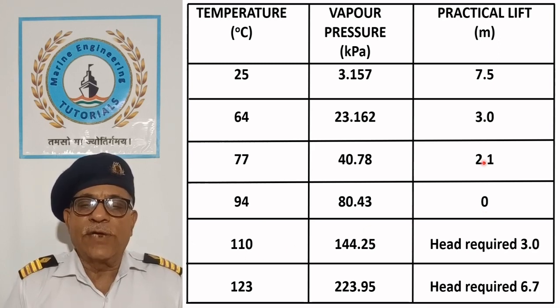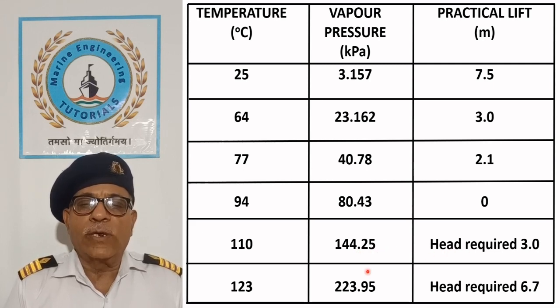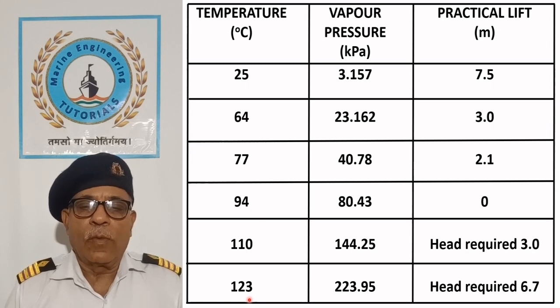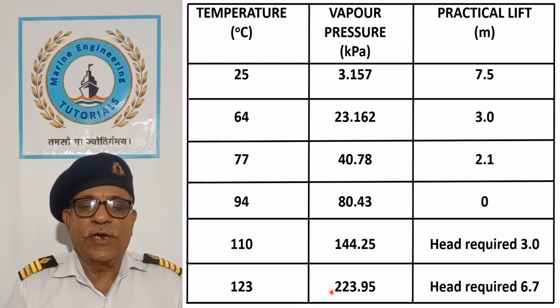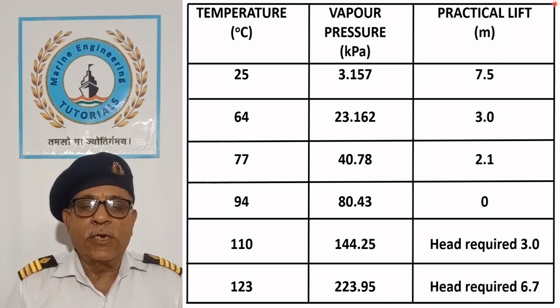At 110°C, vapor pressure is 144.25 kPa; the pump now needs a head of 3 m to draw the water. Similarly, when water temperature is 123°C, vapor pressure becomes 223.95 kPa and the pump requires a head of 6.7 m to draw the water.